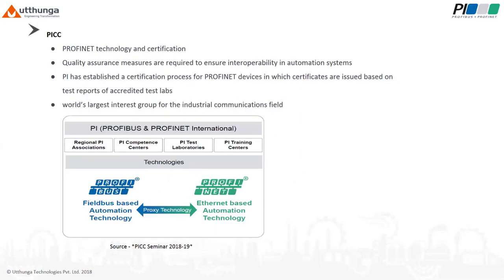Profinet technology and certification. Appropriate quality assurance measures are required to ensure interoperability in automation systems. For this reason, the PI organization has established a certification process for Profinet devices, in which certificates are issued based on the test reports of authorized test labs. As I said earlier, there are test labs all over the world that are authorized by the PI organization. And for any field device, if a manufacturer is releasing a Profinet device, it should be tested by an authorized test laboratory. That is mandatory.